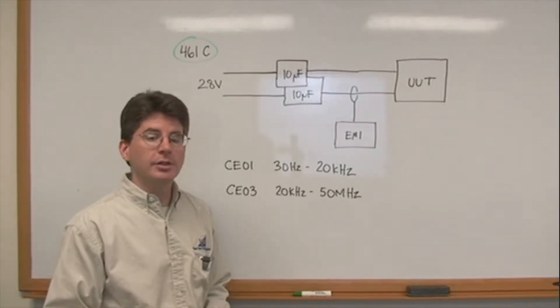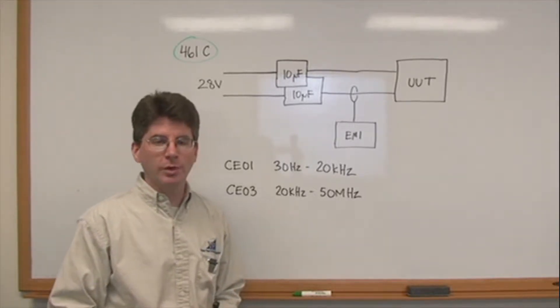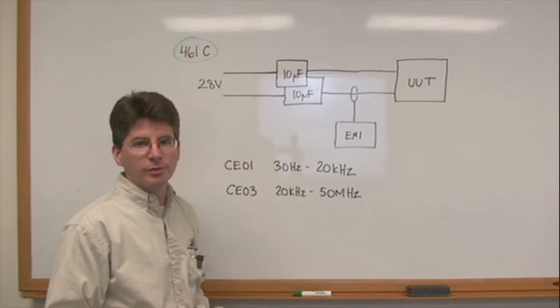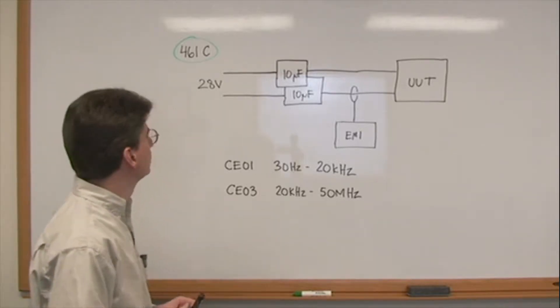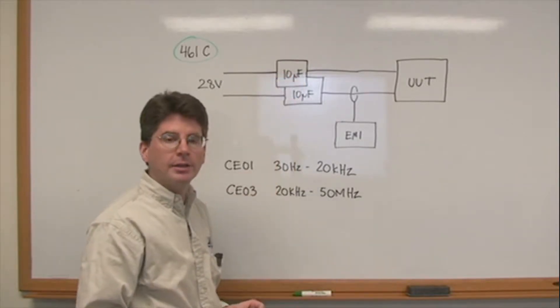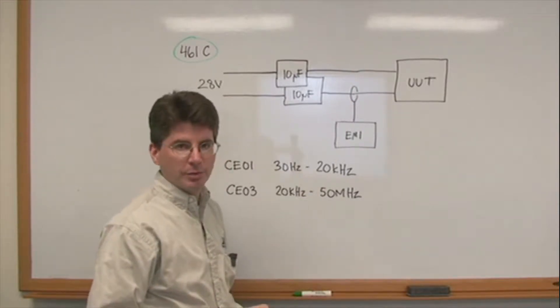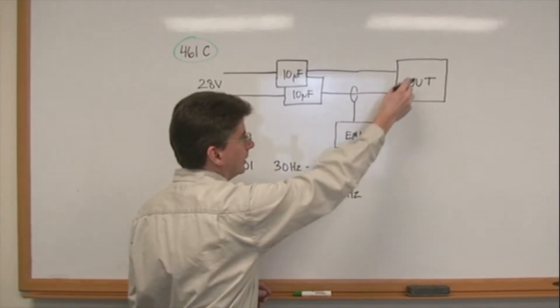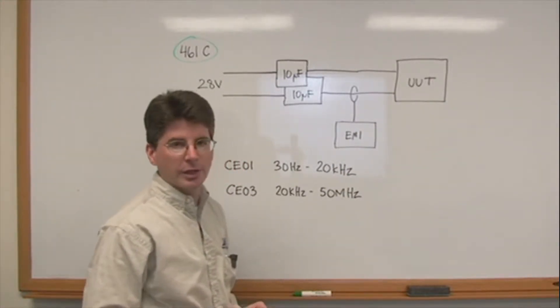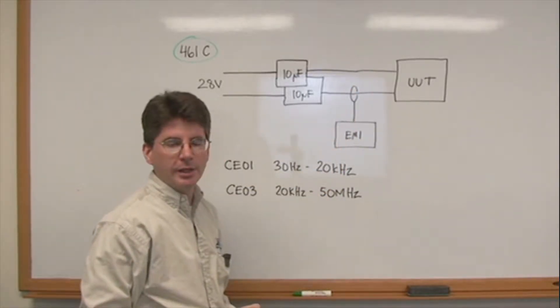This is the setup for measuring conducted emissions according to MIL-STD-461 revision C. This is an older method and it's similar to what is used for DO-160 conducted emissions. In revision C we use a 10 microfarad feed-through capacitor and a clamp-on current probe to measure the conducted emissions on the input line to the UUT or unit under test, which is the DC-DC converter and associated EMI filter. So the current probe will feed into the EMI analyzer.